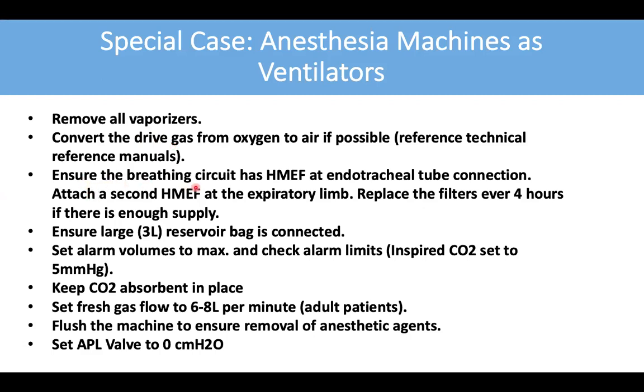Again, you'll ensure that the breathing circuit has an HME filter at the endotracheal tube connection. You'll attach a second filter at the expiratory limb. The recommendation is that you replace these filters every 4 hours if there's enough supply. Ensure that a large reservoir bag is connected. You will set the alarm volumes to maximum and check the alarm limits. As an example, the inspired carbon dioxide alarm needs to be set at 5 millimeters of mercury.